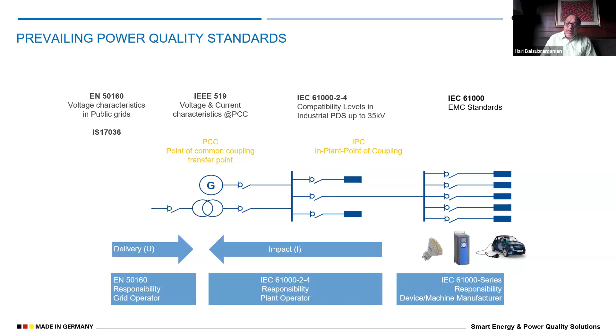For example, on the consumer side, the utility will come and say don't pollute my system beyond 5% of harmonics, don't throw more harmonics into my system, your limit is 5%, you can throw but it's limited to 5%. So there is a limit which is set. We only try to follow the limits rather than trying to understand what is happening inside our system, inside our load sites for example. This is much more difficult.